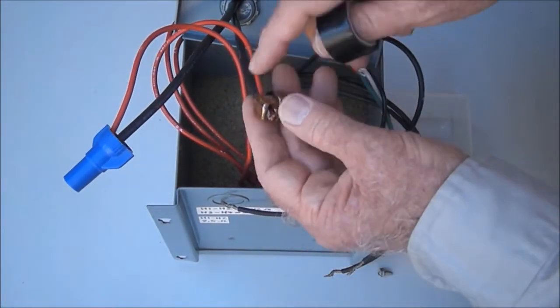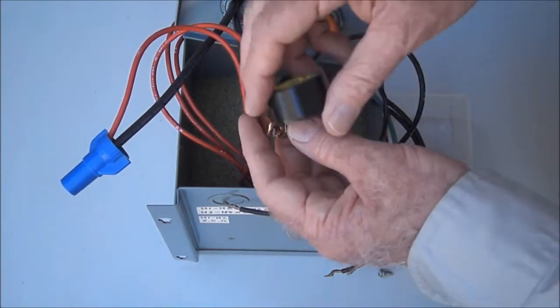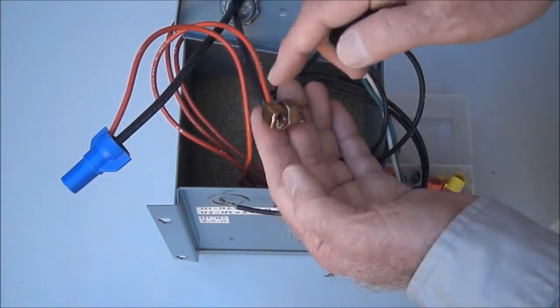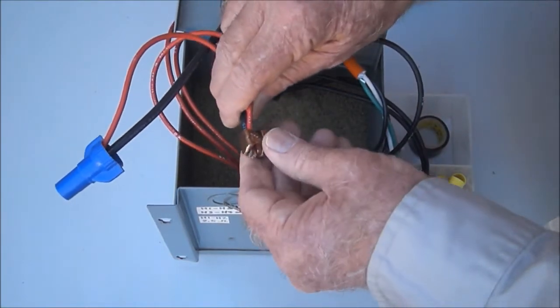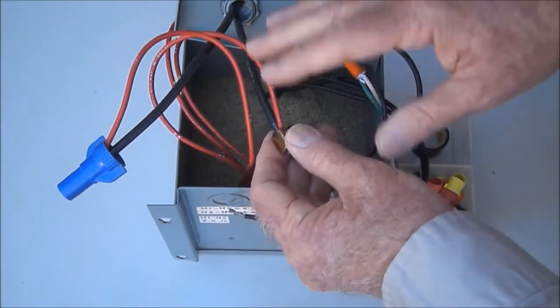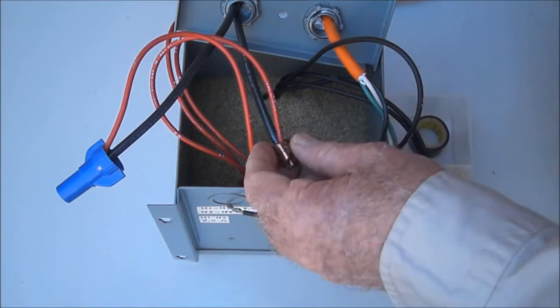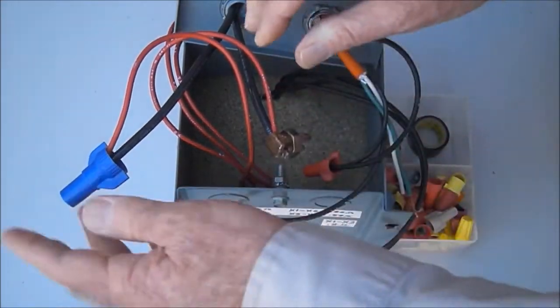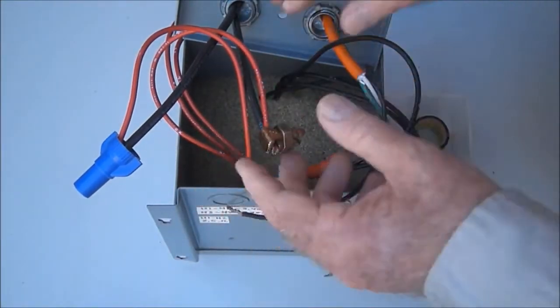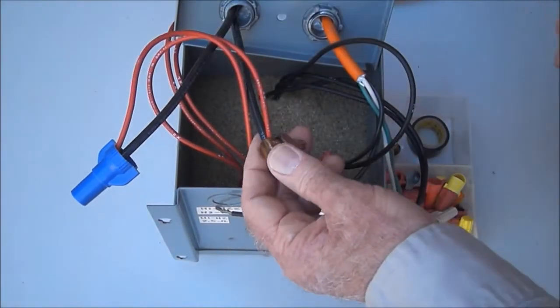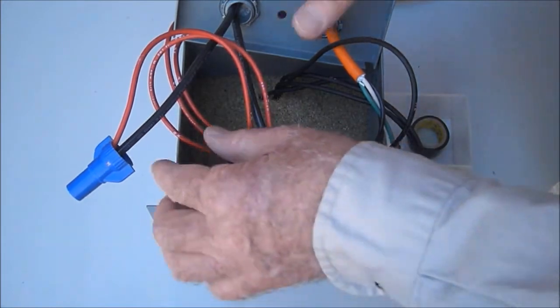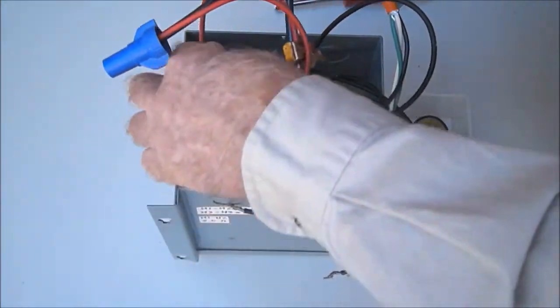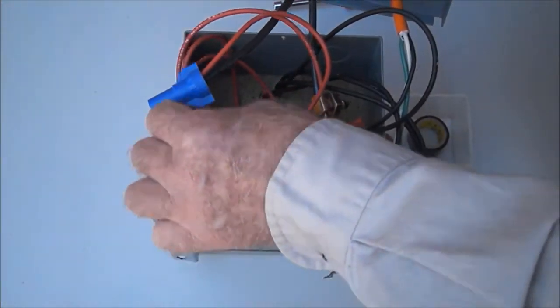Once you've done that, you would cover the entire wire nut with layers of black electrical tape to make an insulated connection that will separate it from all other conductors inside the wiring compartment. Whether you use wire nuts or a split bolt, you have the same type of wiring integrity that you need to install the transformer.